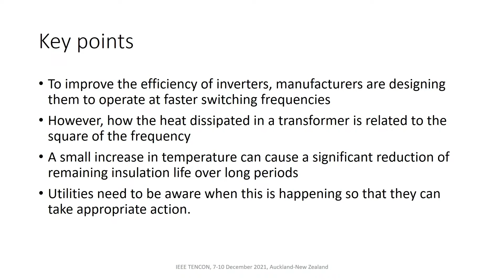As I mentioned before, the life remaining of a transformer is a function of the condition of its insulation paper. This isn't to say that the transformer definitely fails on the condition of the paper. The transformer can fail on other aspects, something else going wrong with it, or even corrosion of the tank can be quite significant. However, the paper is the main core thing. When the paper has reached its end of life, then you can't really replace it.